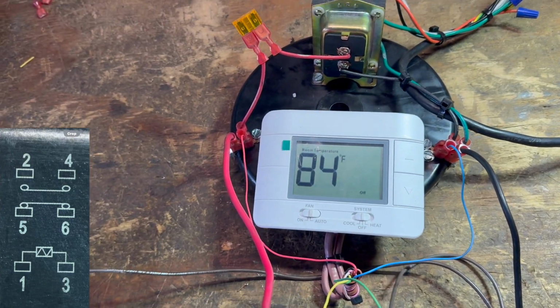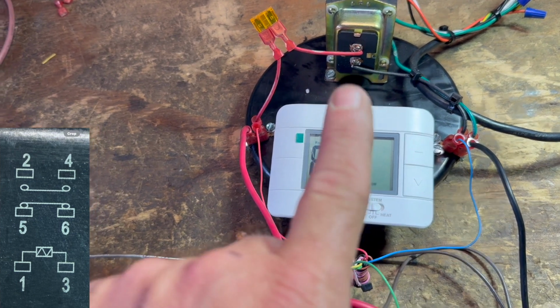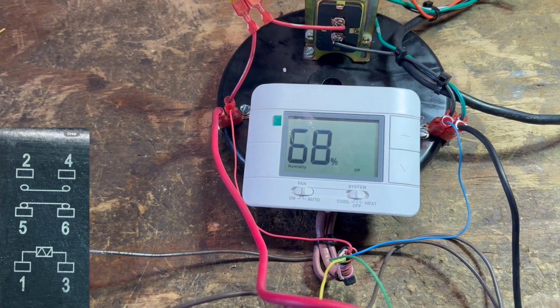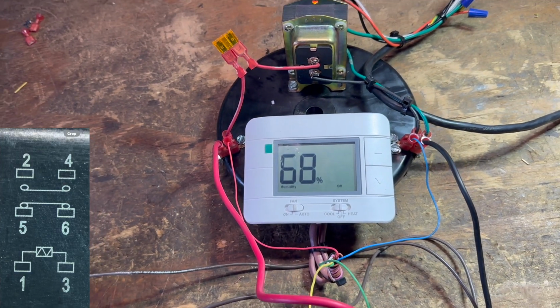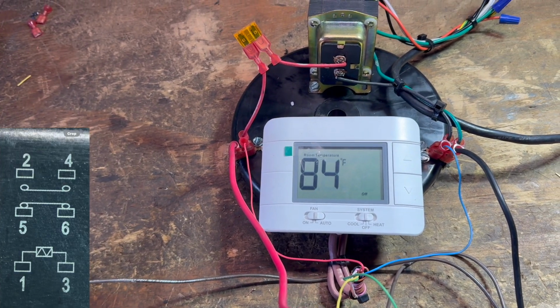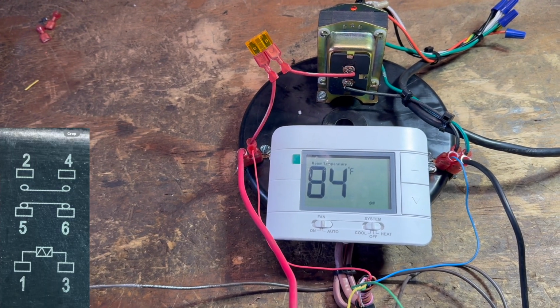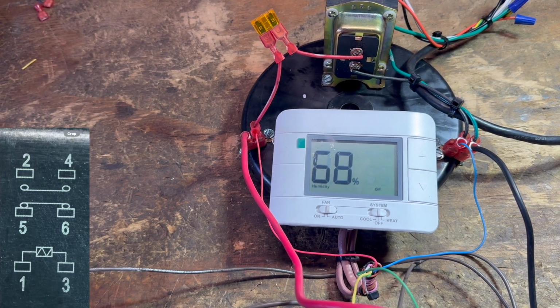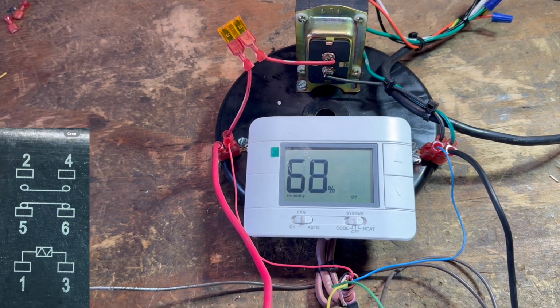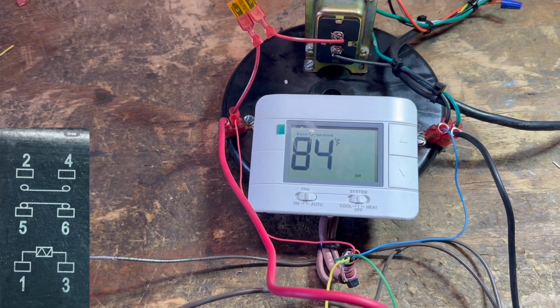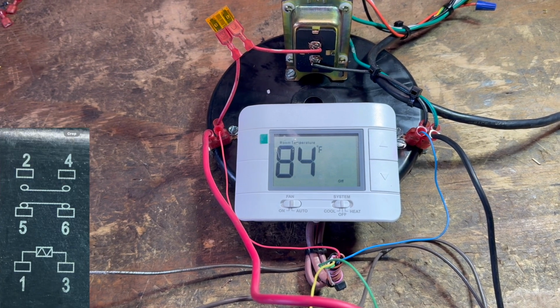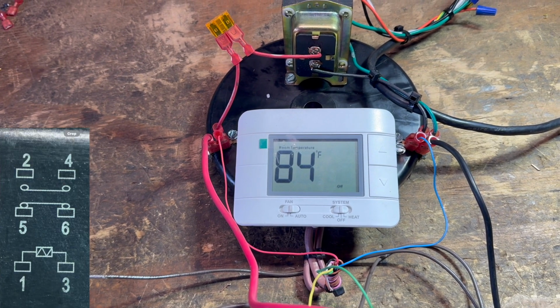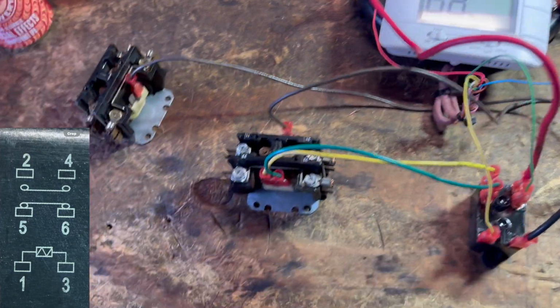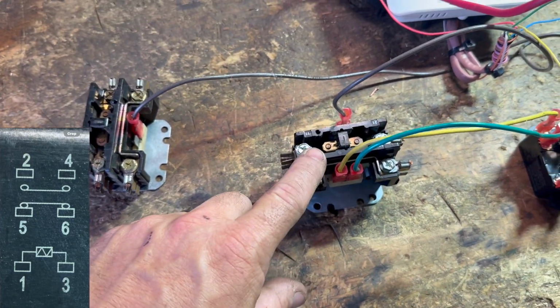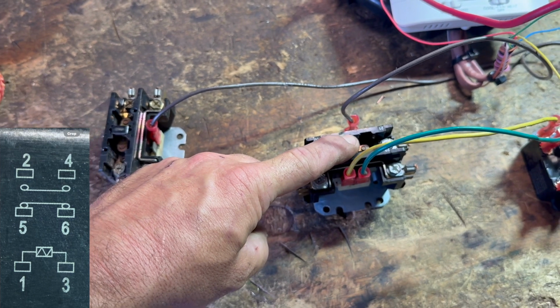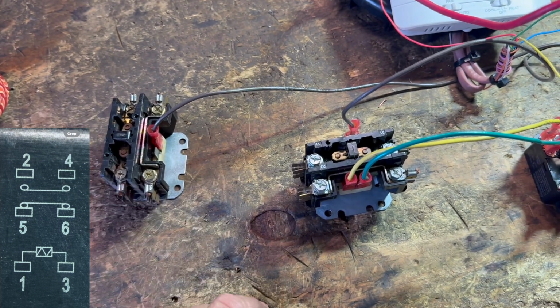So it switches that 24 volts to all sorts of different wires inside this thing to tell what pieces of equipment you want to come on. So I've actually messed with thermostats and just said, hey, turn on the fan, and it will turn on a light, or let's put it in cooling and it will start playing music on something else. They're just control signals. That's all it is. It's 24 volts AC, which is either on or off when you're activating smaller loads like a contactor. 24 volts makes this come on, and then the release at 24 volts makes it come off.